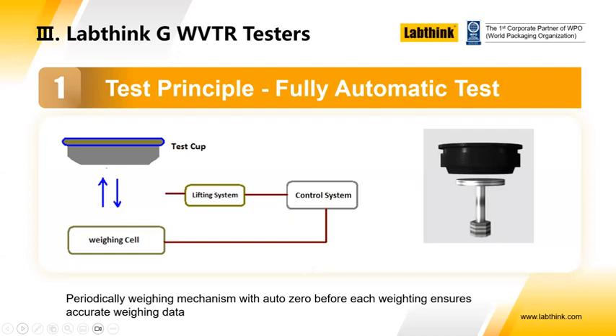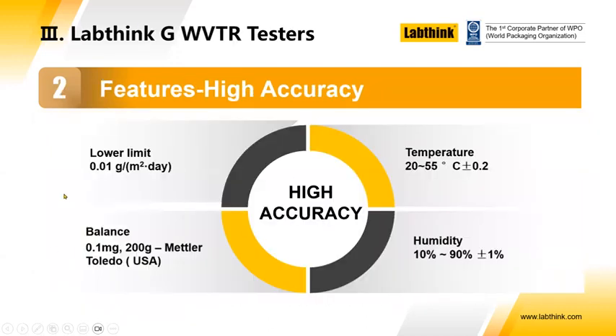And in doing so, that increases the repeatability and the trustworthiness, if you like, the reliability of the measurements that you take using this system. It's high accuracy, as I said, with advances in the technology and improvements in the measurement devices that are available, we can say that the lower limit is 0.01 grams per meter squared per day. The balance is 0.1 milligram up to 200 grams, a Mettler-Toledo balance, and sometimes with heavy or very permeable specimens, the capacity of the scale can be increased. Temperature range, the control range of the chambers incorporated with the instrument is between 20 and 55 Celsius plus or minus 0.2, with a humidity range of 10 to 90% plus or minus 1%.